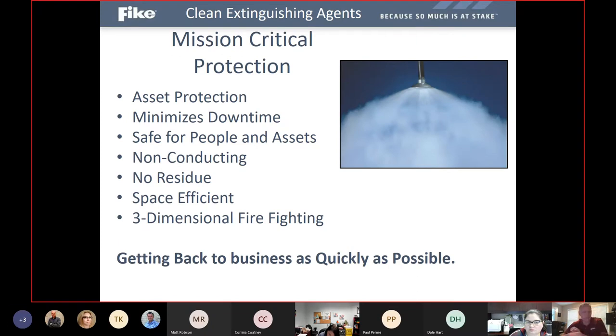Clean extinguishing agents have been around for a very long time and have always been the most preferred choice for fire extinguishing and fire protection, especially in mission critical protection areas, where the primary goals of a system are to protect the assets and minimize downtime. They are also very safe for people, because a lot of these areas are normally occupied and occupiable, non-conductive of electricity, leave no residue behind, are very space efficient, and provide three-dimensional firefighting. Discharging as a gas in the room, it'll get in and around any obstructions, any small open passageways inside cabinets, server racks, wherever that smoldering or fire event may occur.